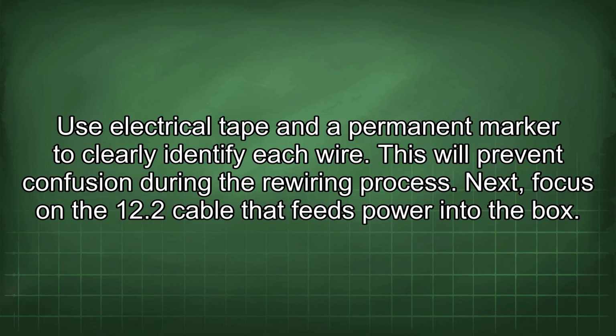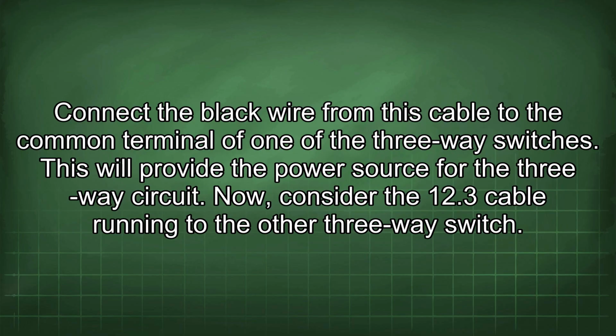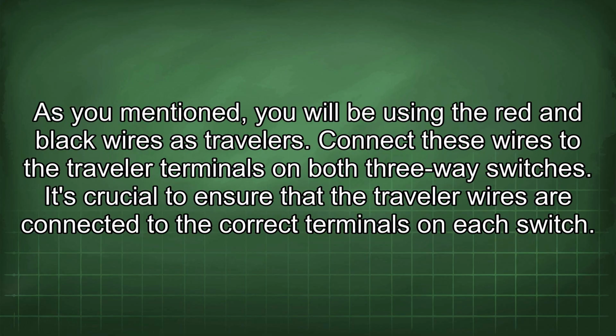Next, focus on the 12/2 cable that feeds power into the box. Connect the black wire from this cable to the common terminal of one of the three-way switches. This will provide the power source for the three-way circuit. Now consider the 12/3 cable running to the other three-way switch. As you mentioned, you will be using the red and black wires as travelers. Connect these wires to the traveler terminals on both three-way switches. It's crucial to ensure that the traveler wires are connected to the correct terminals on each switch.